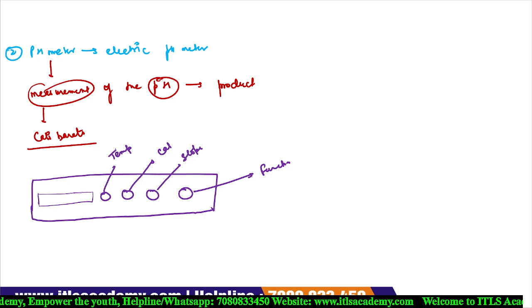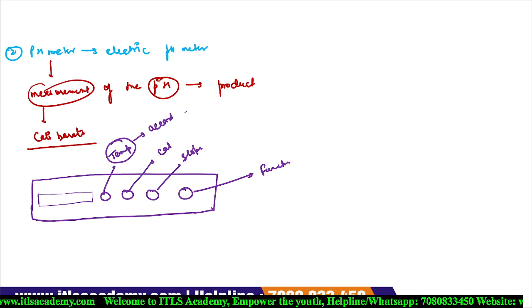Now, what we have to do, we have to set the temperature, and this temperature is set according to the buffer that we use. Okay. Now, what is the buffer? For the calibration of the pH meter, we require two types of buffer solution. The one is your pH 7 and another one is your pH 4.